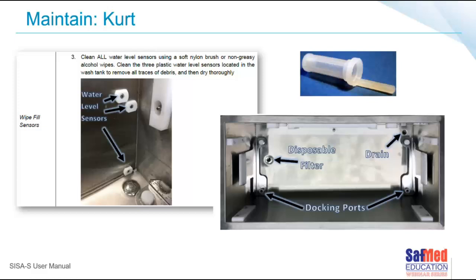So with the irrigation connecting up, as you can see, there are docking ports. If you have irrigation, this is a fully automated unit. The filter will stop the debris from going through the lower pipe and connectors and through any lumens. It stops the debris from pushing through into your lumen devices and the water manifolds. Okay, now I get it, so they're connected correctly, and that traps all that debris. So it's quite important that we check that every day and replace it as instructed.